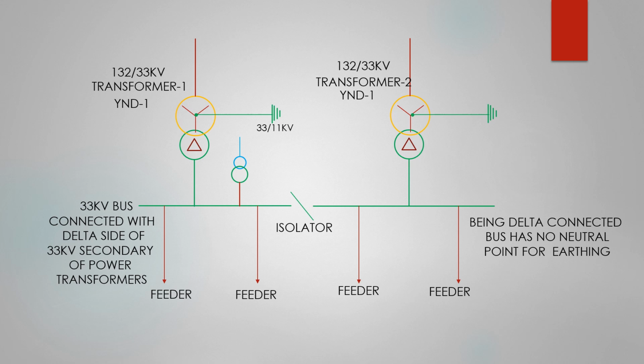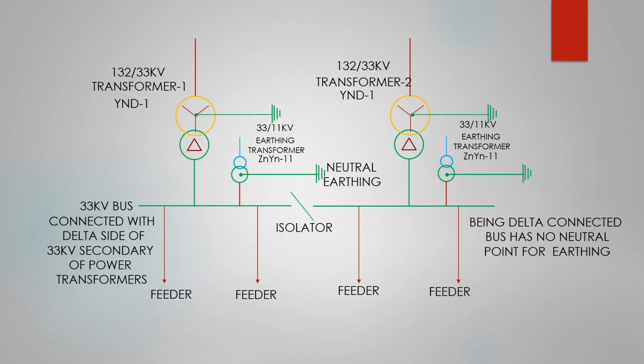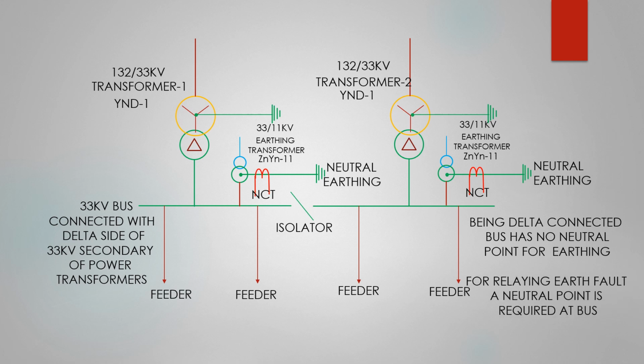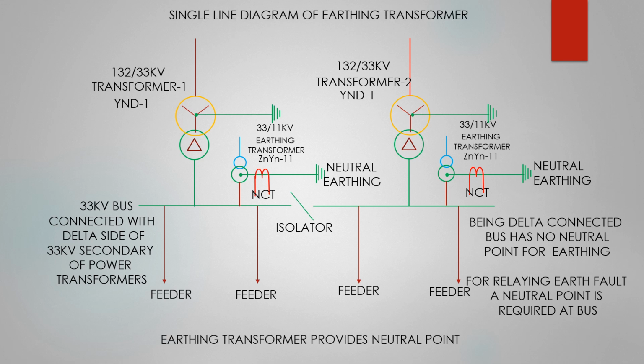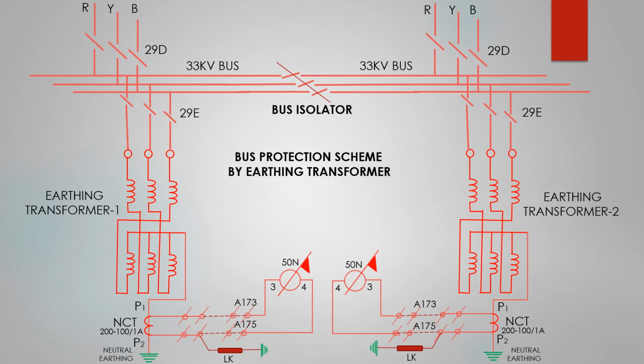So, earthing transformers are provided to solve this problem by creating a neutral point at the bus for relaying the earth fault relay through the neutral to protect the bus. This is the circuit diagram of the bus protection scheme by two earthing transformers for two star delta power transformers. Two power transformers of star delta connection are made parallel by closing the bus segregating isolator.